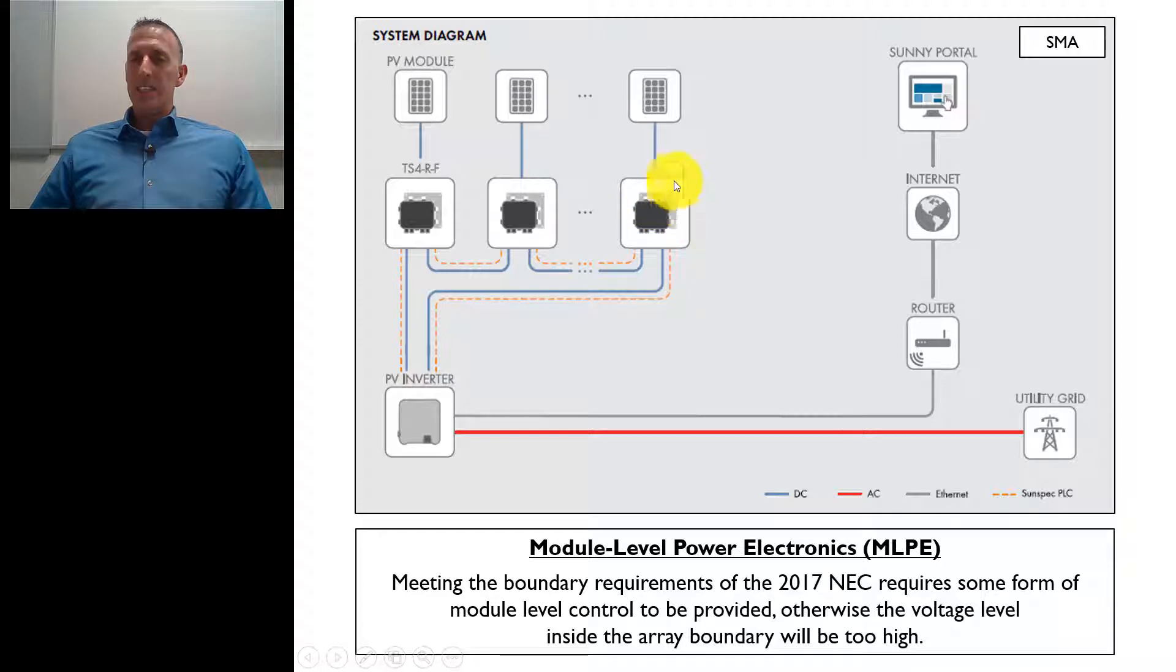These are DC to DC converters, or that's the concept behind those. And then these are tied all the way down into an inverter, where the inverter would control these modules. This is like the master. These are the slaves. The modules would provide a certain voltage and current, and the inverter would control what the total voltage and current of the system would be.